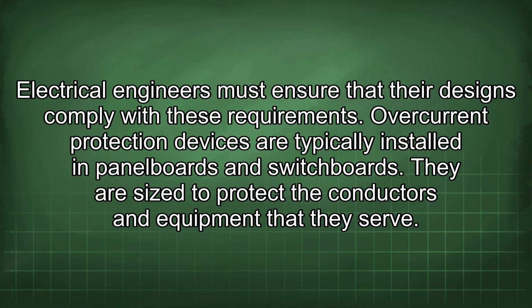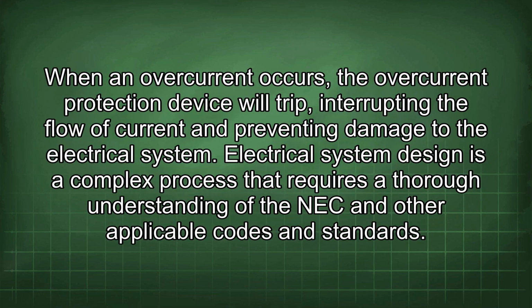Overcurrent protection devices are typically installed in panel boards and switchboards. They are sized to protect the conductors and equipment that they serve. When an overcurrent occurs, the overcurrent protection device will trip, interrupting the flow of current and preventing damage to the electrical system.